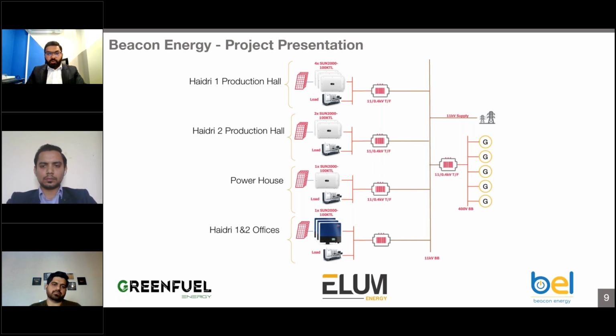The old system was installed on offices and integrated at the LT room side on the generator side. They have 5 different generators, which were synchronized with the DeepSea controller. The main criteria was to integrate the solar system with the synchronized generators, and also to stop reverse feed to the grid, since we have an 11 kV supply over there. It was a very complete system.